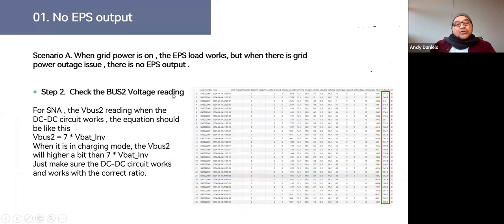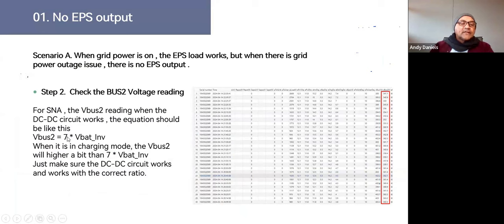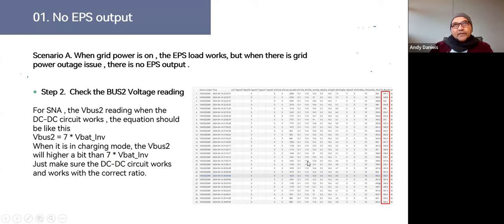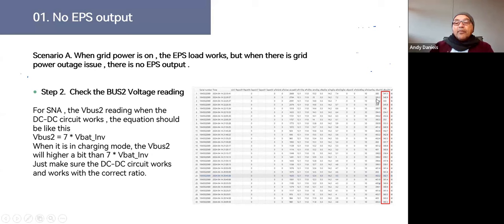The BUS2 voltage column is key. For the SNA, when the DC-to-DC circuit is working, there's a specific ratio. For the SNA6, the multiplier is 7 — so if battery nominal voltage is 50 volts, BUS2 should read 350 volts (50 × 7). For the SNA5, the multiplier is 6, so 50 × 6 = 300 volts. This is how we confirm the DC-to-DC circuit is working correctly. If we get the expected value, the circuit is working perfectly.